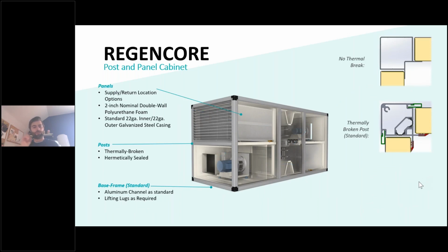And then for the cabinet, on the standard units, we use a post and panel style of cabinetry, 2-inch foam injected panels, much the same as our other ones with our air handlers. But importantly here, and what I find with this style of unit, is we use a thermally broken post. So when we were testing at extreme temperatures without a thermally broken post, we found that there was frost propagation from the corners of the unit. And then once putting in that thermally broken post, it eliminated it completely.